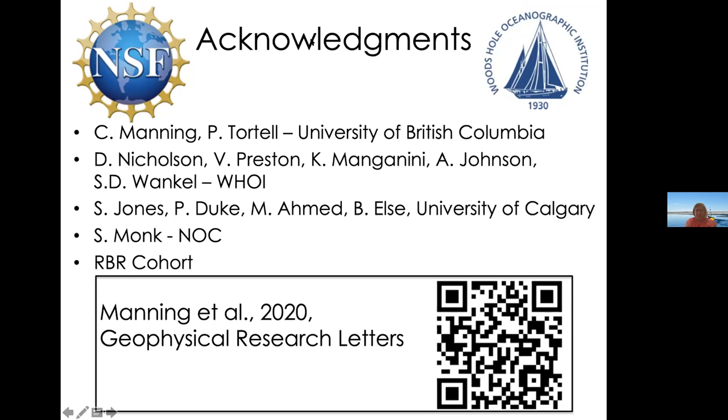Thanks Anna, that was very interesting. A question from Jean Damien: How often would you recommend calibrating the CH4 sensor installed on board your platform? We usually calibrate it before and after going into the field. The nice thing about it being an atmospheric sensor is that as soon as you go from the water to the air, it drops back to atmospheric levels, so you can do a quick check to confirm you're measuring about the right value — the values are so different from being in the water.